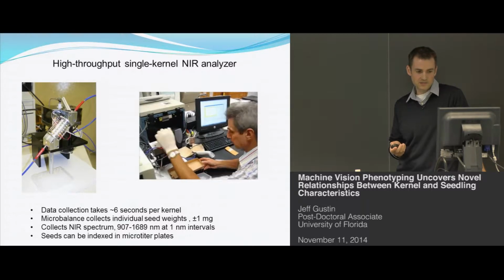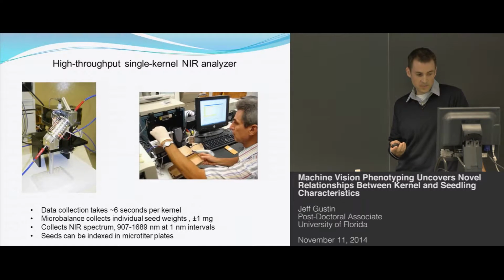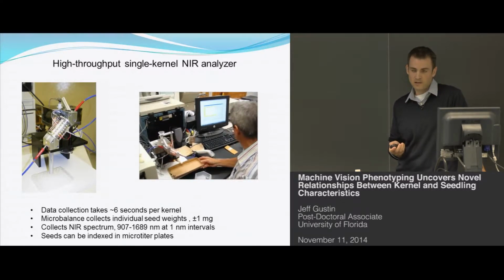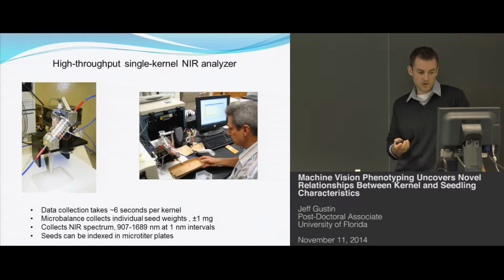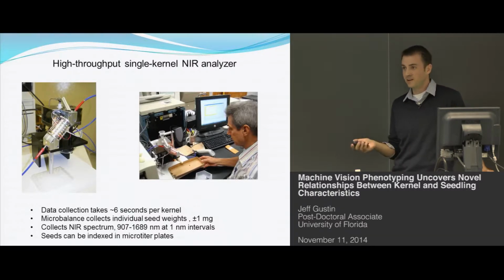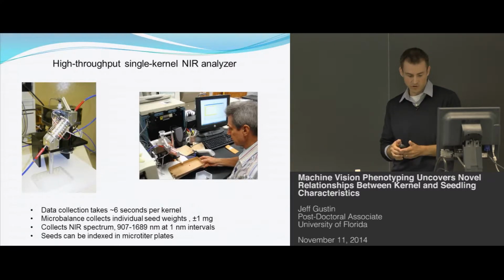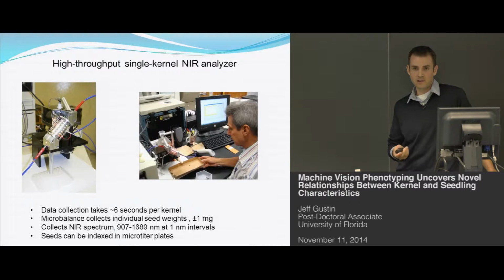It takes about 6 seconds for every kernel to fall through. And in that 6 seconds, the microbalance collects a seed weight to within 1 milligram. It collects an NIR spectrum from 907 to 1689 nanometers at 1 nanometer interval. So you're getting 790 different wavelengths for each kernel that falls through. And as I said, the seeds can be indexed into microtiter plates so they're all kept organized.